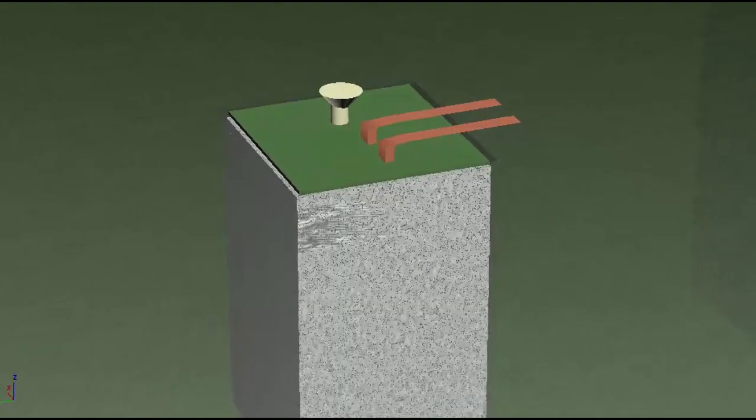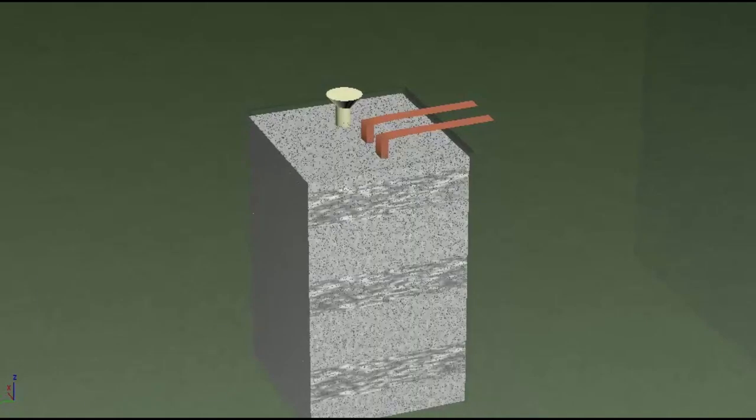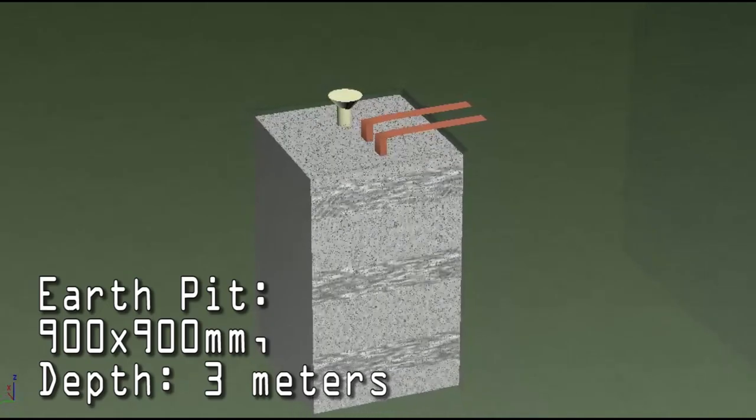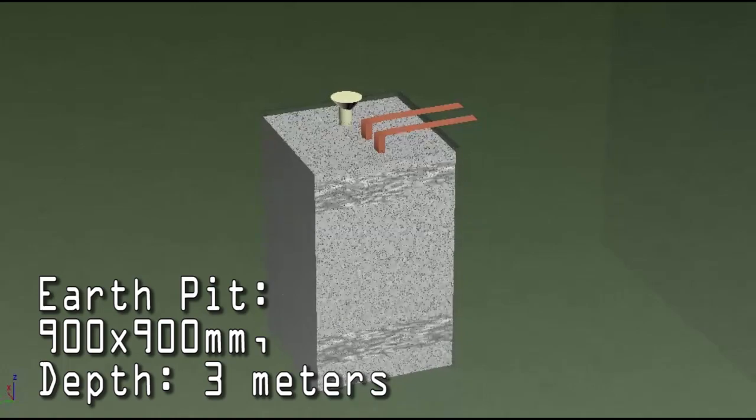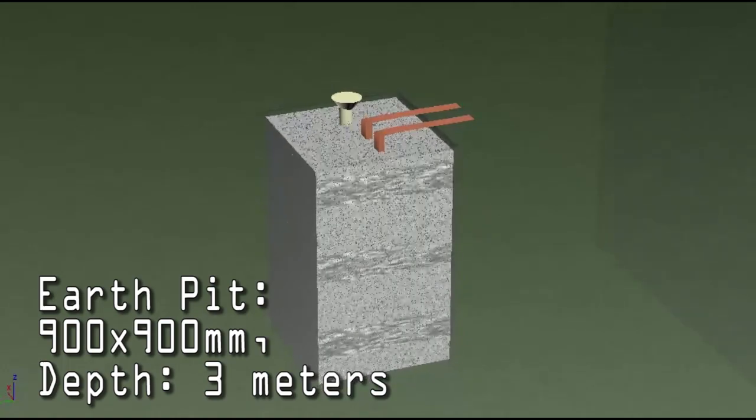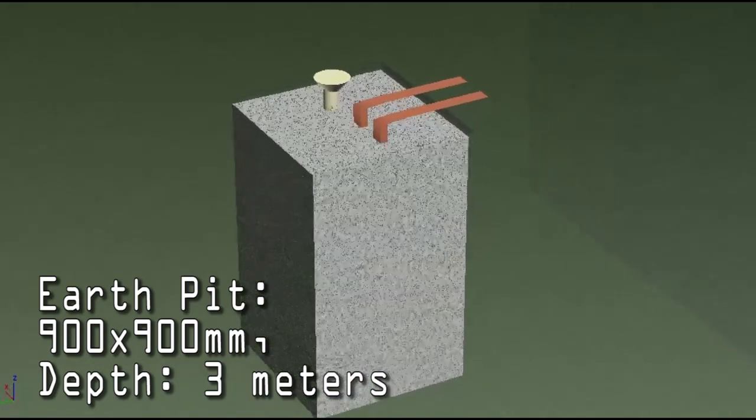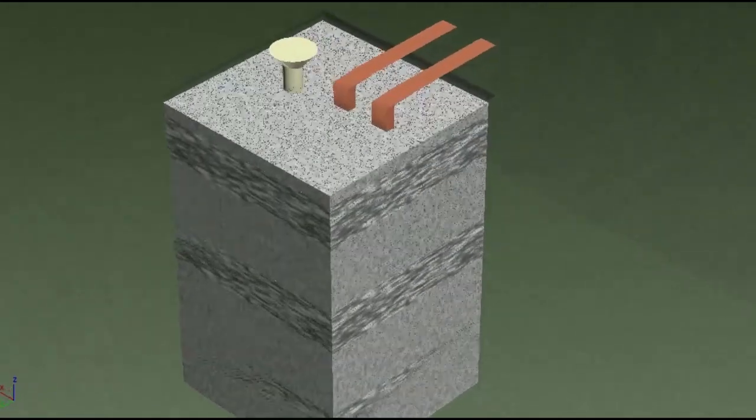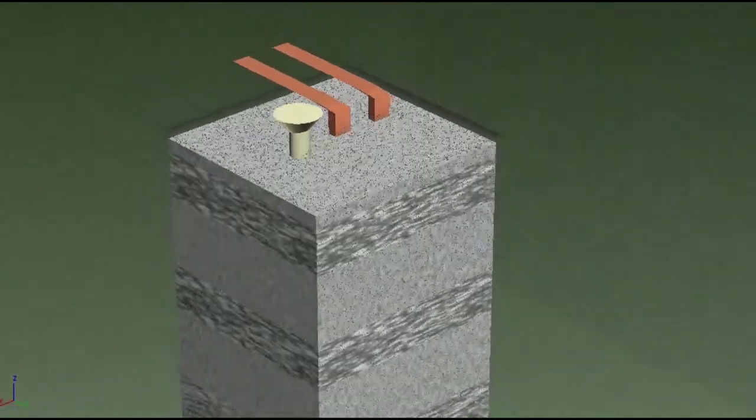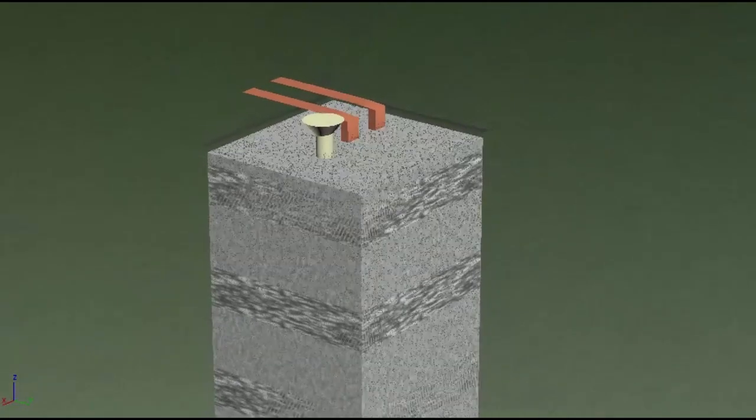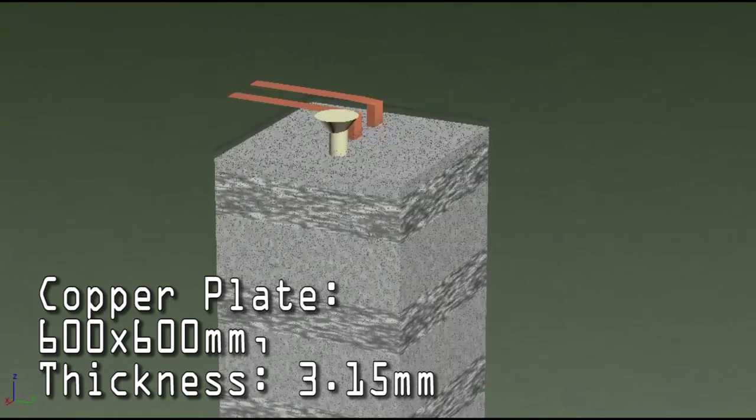The dimensions of the earth pit should be 900 mm by 900 mm and it should be around 3 meters deep. Inside the salt and charcoal layers, a copper plate of size 600 mm by 600 mm and thickness 3.15 mm is positioned in the middle.